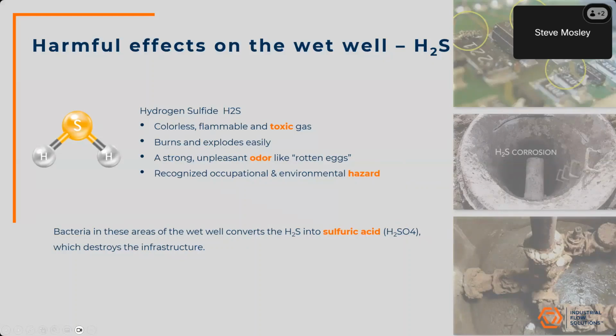One of the primary components we want to talk about is hydrogen sulfide gas. This is a flammable and toxic gas, which is an occupational and environmental hazard. This commonly builds up in wet wells and can cause significant damage to the equipment within it. It does have a rotten egg odor, so it does contribute to the odors that are typically associated with lift stations. And when you have bacteria in these wet wells, it can break down the hydrogen sulfide into a sulfuric acid. And that sulfuric acid causes much of the damage that you'll see on the right-hand side of the slide with corrosion of metallic components, corrosion of the concrete. And if it makes its way up through the conduits into the control panel, you'll see corrosion on the printed circuit boards and electrical components as well.